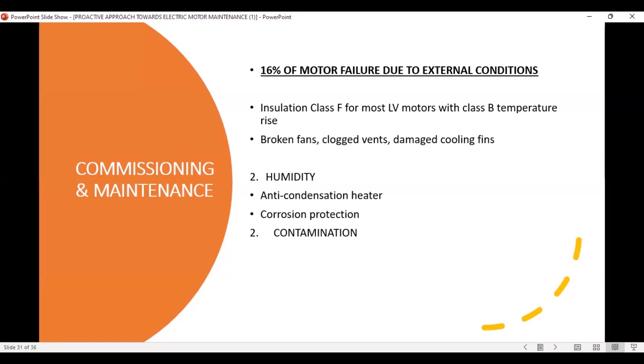And in a humid environment, if the motor is operated in a humid environment, the anti-condensation heaters must always be working. Whenever the motor stops, it has to be designed in such a way that immediately it stops, the heaters come in to take over so that condensation will not take place for the bearings to fail. And contaminations contribute to a lot of motor failure. We must ensure that motors are protected. If they need canopies, we ensure they are protected from all the external environmental effects for the motor to last longer.